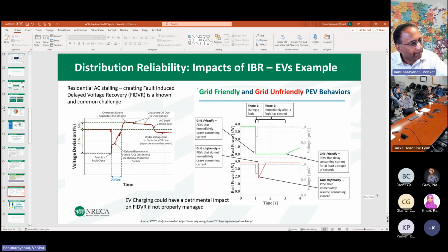to maintain reliability. The other one is, when you look at EV charging, what does that do to residential AC stalling? So basically, this is a well-known problem: fault-induced delayed voltage recovery. It's caused by residential AC stalling, and the point here is that you need to have the right settings on your EV chargers. If not, it can make the problem worse in terms of voltage recovery. If you have an EV plugged in and charging when the fault occurs, the behavior of the inverters on the EV can make the problem worse. You can get into details of this, but essentially all this points to a need for looking at what settings you need on the inverters to make sure they are grid friendly and not grid unfriendly. And that's again an evolving research area.